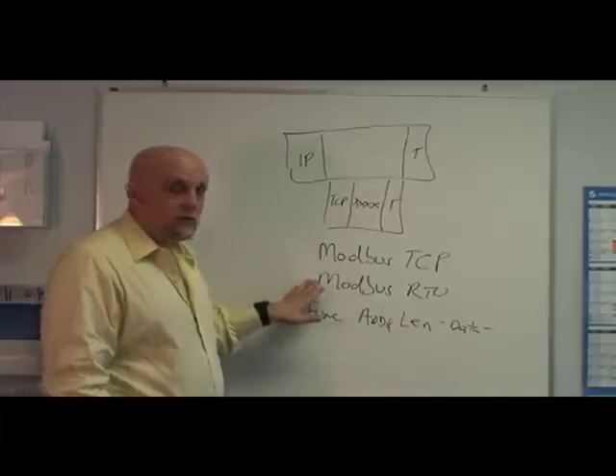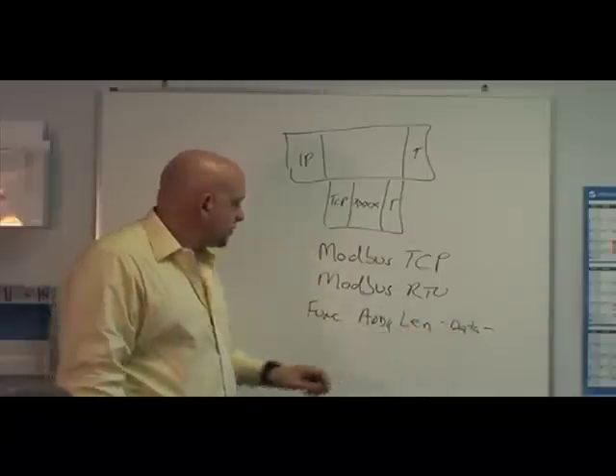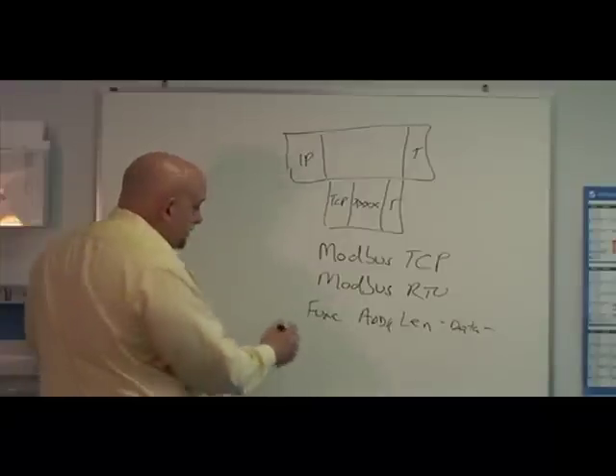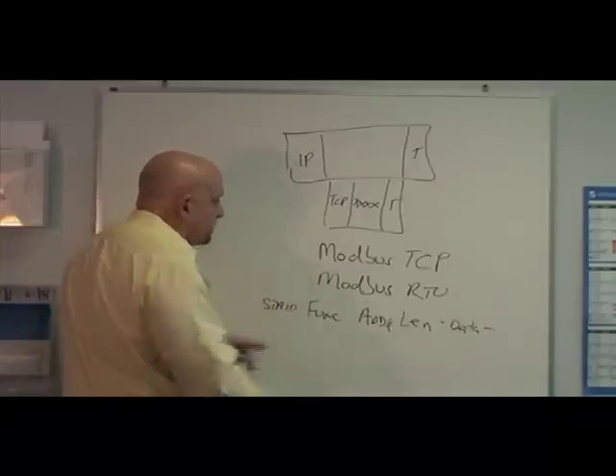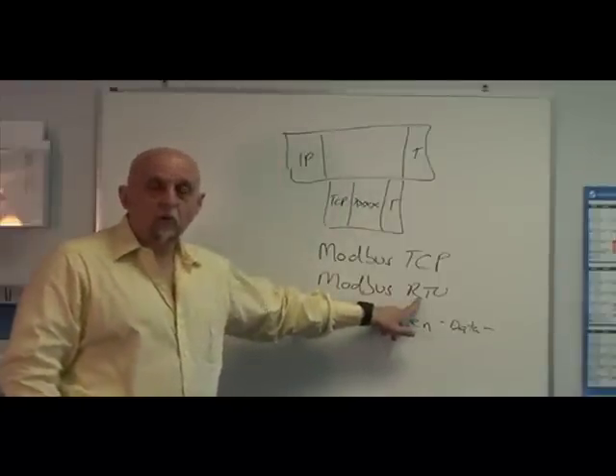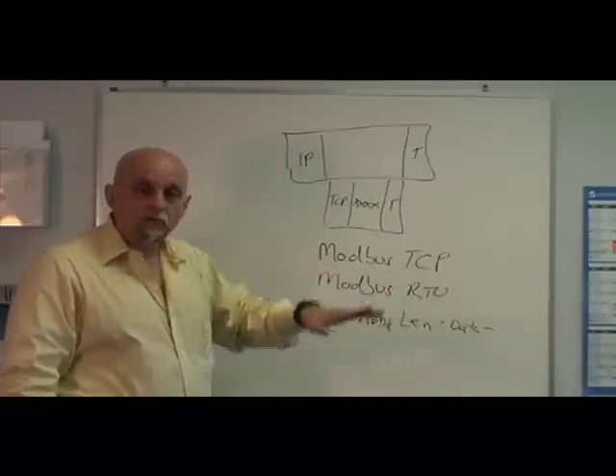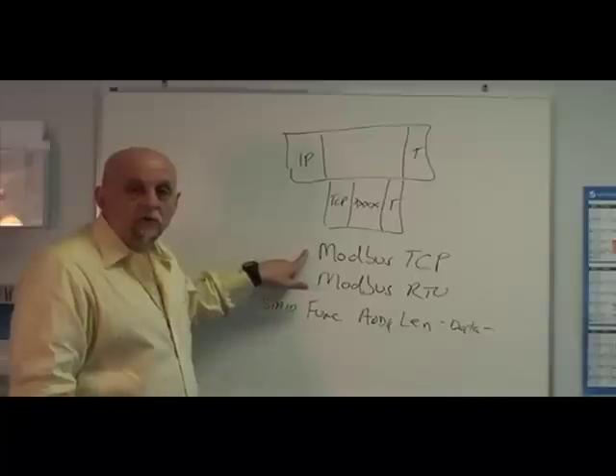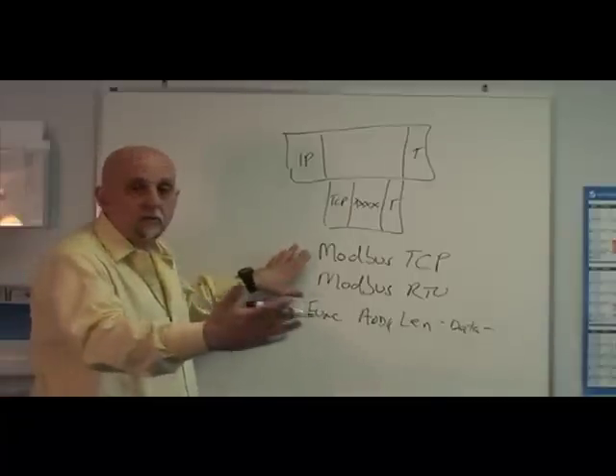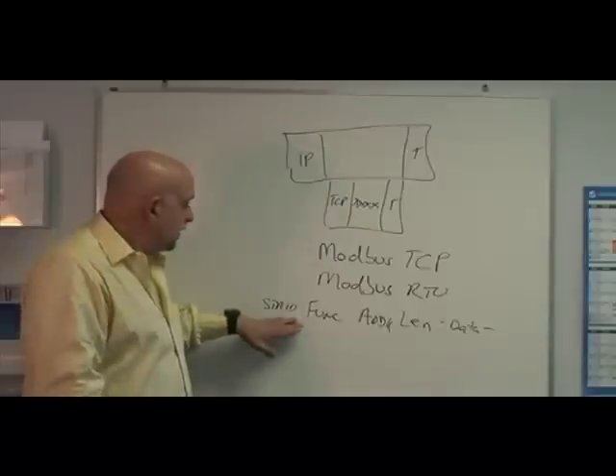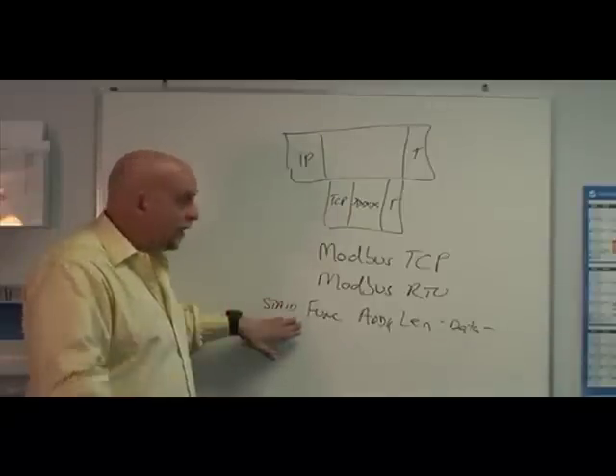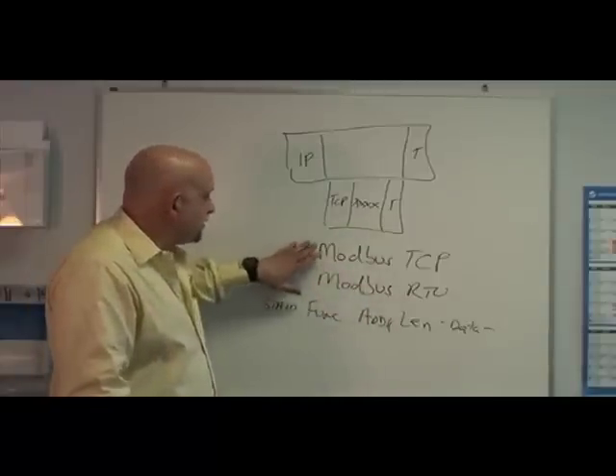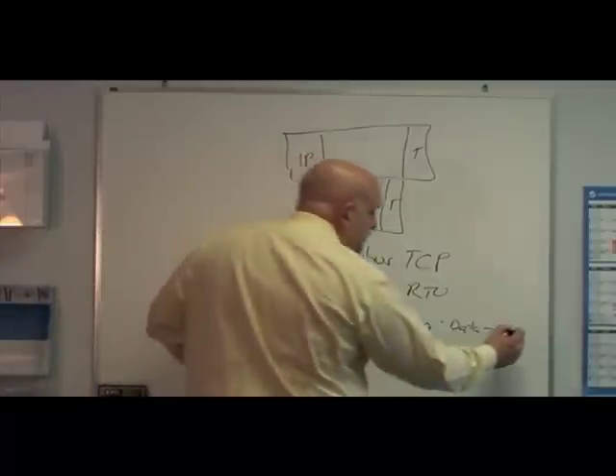Now, Modbus RTU is the same kind of message structure. It's actually got an address on the front, a station ID on the front, because Modbus RTU is on RS-485, so that's a multi-drop network, so you need a station ID to indicate which particular device. On Modbus TCP, we don't use that because we've got an IP address. We've made a connection with a specific IP address. On 485, you have to identify the station it's going to. So that's really the only difference between it. On Modbus TCP, on Modbus RTU, we also have a CRC at the end.